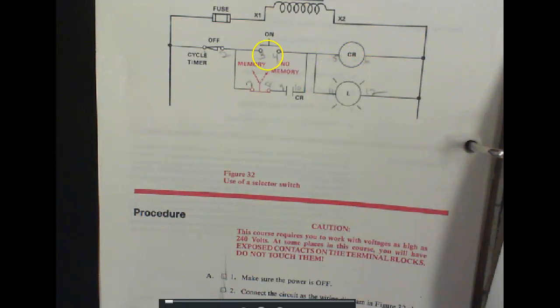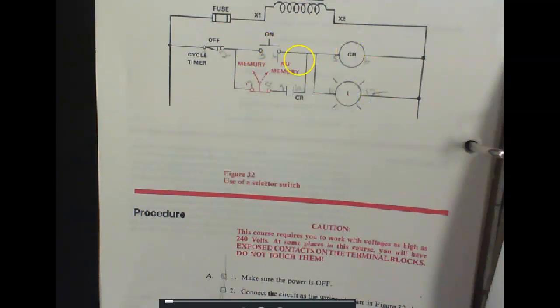So if I put it in memory, then when I touch that button right there, it's going to energize CR. This is a CR contact, it's got the same name, and it's going to seal itself in. So now you can let go of the start button, right? Everybody okay there? Okay, until I come up here and activate the limit switch, and it should drop out.